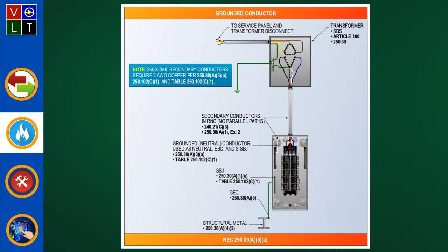250.102(C)(1), but it shall not be required to be larger than the largest ungrounded phase conductor. So when I go a little further, it tells you that the grounded neutral conductor shall not be smaller than 12.5% of the circular mil area of the largest ungrounded phase conductor, for sizes larger than 1100 kcmil or 1750 kcmil aluminum. So you're seeing we're applying the exact same requirements here, whether it's the supply-side bonding jumper or the grounded conductor. Now, if I go to the next one, this is where you get into the parallel portion of it.